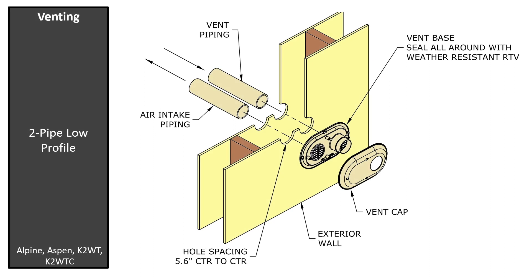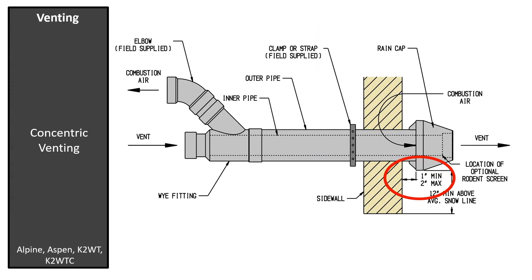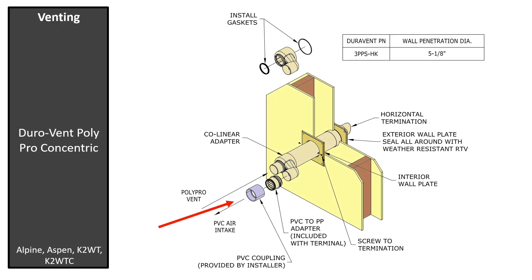Low profile venting can be installed with the vent termination on the left or the right if installed horizontally. If installed vertically, the vent termination must be at the top. Do not install the vent terminal at the bottom due to cross contamination of the flue gases. When concentric sidewall venting, the distance from the concentric air inlet to the wall must be a minimum of 1 inch and a maximum of 2 inches. The polypropylene concentric kit includes a polypropylene to PVC adapter for the air inlet. The vent must remain rigid polypropylene back to the boiler.